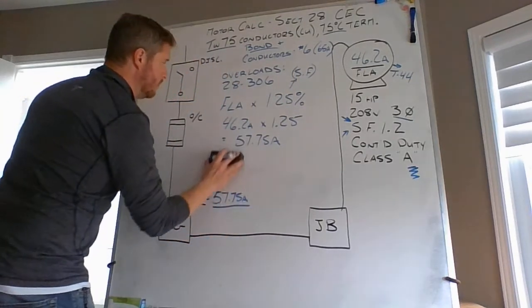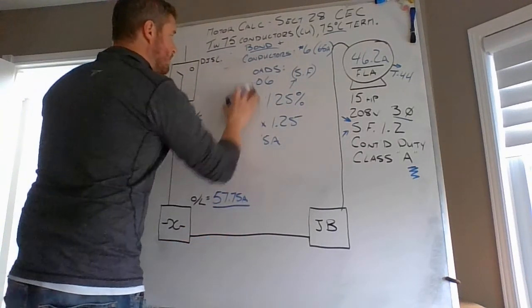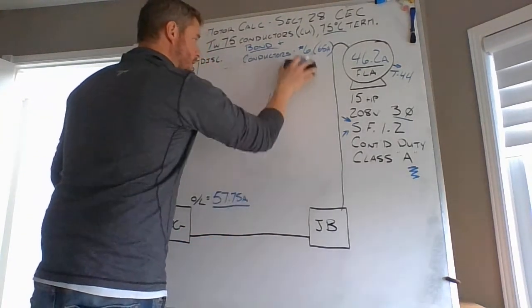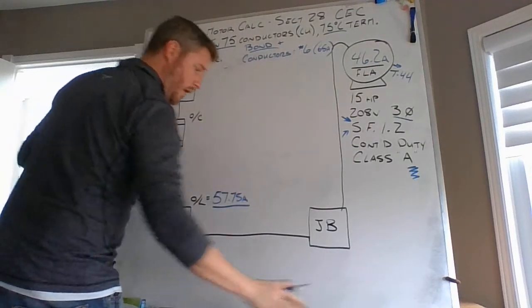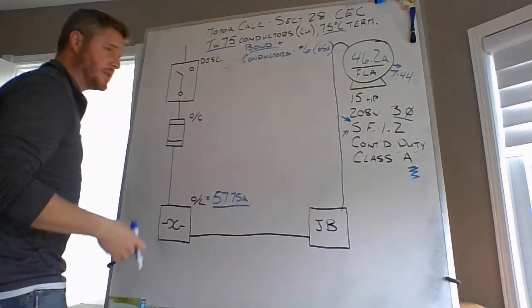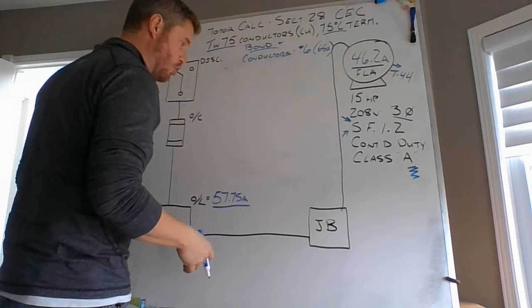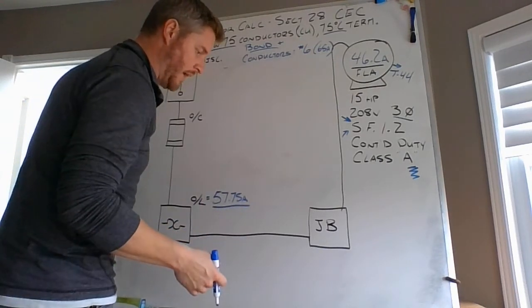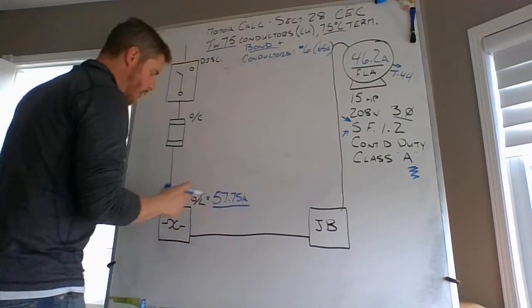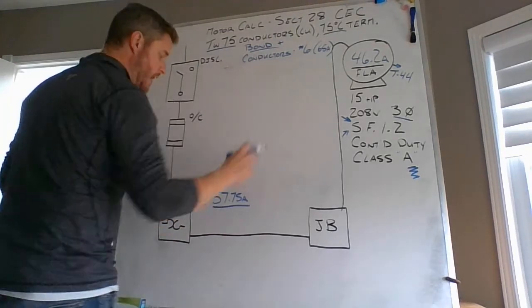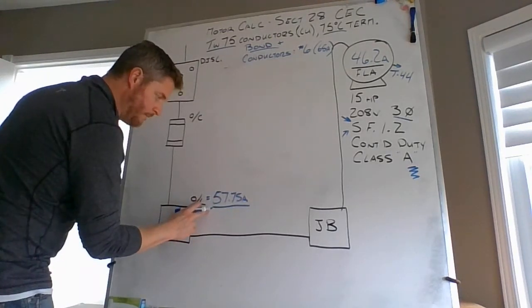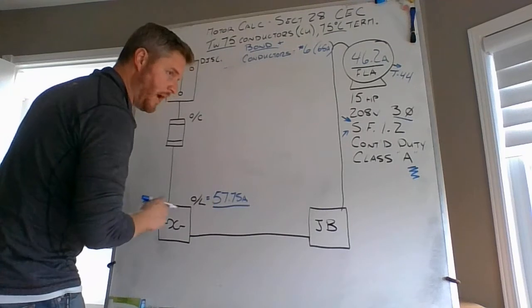This proves to you that your overloads protect your conductors. Now, I understand that there was something going on with your motor installation book, your motor control book, and we'll address that on Friday. That's not a big deal. But your overloads are protecting your conductors. Your overloads will open at 57.75 amps.